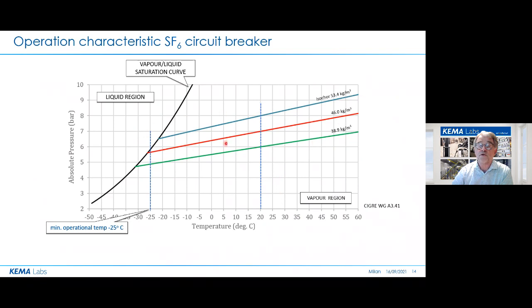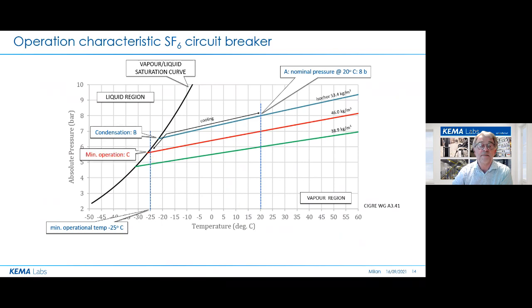At this minimum temperature, sufficient gas, of course, must be inside to fulfill the duties of the device. Well, the drawn lines in this picture are the isochores, which are the conditions of constant amount of gas, constant amount of molecules in the breaker. As initial or nominal condition, we choose 20 degrees and 8 bar, which is a quite safe zone because there is more than enough gas inside. But we see two mechanisms of loss of gas here. First is the cooling and the condensation at point B, to end at the minimum condition in point C, at which more and more gas will condense to end on another isochore.